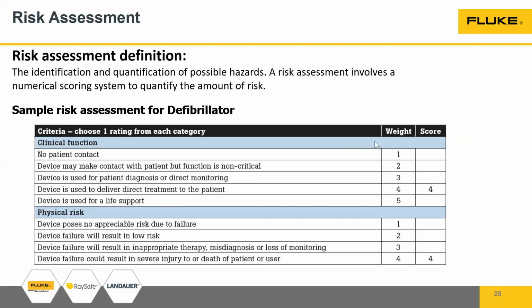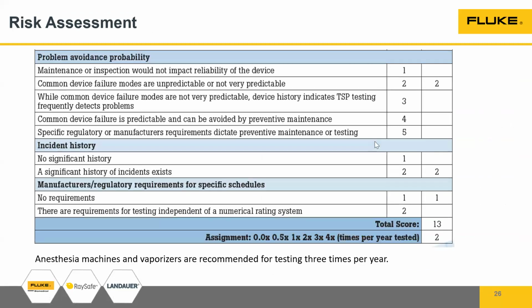Similarly, for a defibrillator we can have this kind of risk assessment done. Clinical function, physical risk, and problem avoidance probability. Based on that, the defibrillator was given a score of 13, which means it has to be tested at least once in 6 months, or twice a year. So, semi-annual.